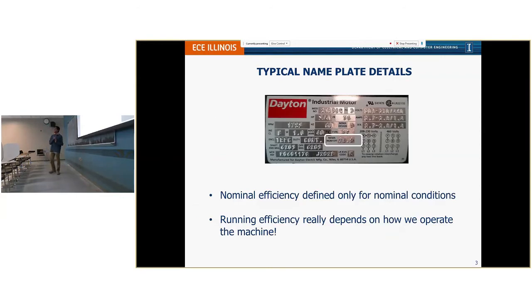This is a typical nameplate of an induction machine, what you'd see on top of the machine. Of concern today is the nominal efficiency — you see a NEMA nominal efficiency. NEMA is the National Electric Manufacturers Association, and they define what's called nominal efficiency. But nominal efficiency isn't everything: it's defined when the machine is expected to operate under nominal conditions, meaning the motor operates around nominal speed, nominal loading or torque, and nominal frequency. There's also something called running or dynamic efficiency, which really depends on how we control or operate the machine, and that's really important.